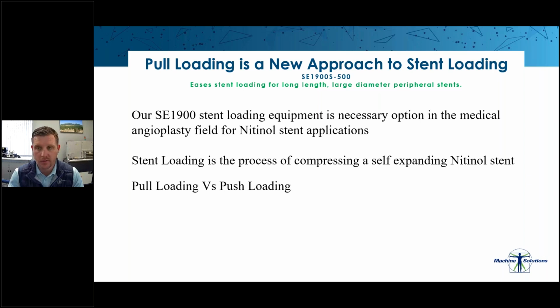While maintaining the compression, the delivery catheter is slid from the proximal side into place underneath the stent and is positioned appropriately. The introducer sheath clamp sits proximally to the crimp head, in between the head and the proximal clamp. The proximal end of the delivery catheter is then clamped into the proximal pull clamp. Using crimp pulse technology to reduce the stiction while under compression, the stent and catheter are pulled into the delivery system sheath, forcing the nitinol stent to maintain its compressed form.